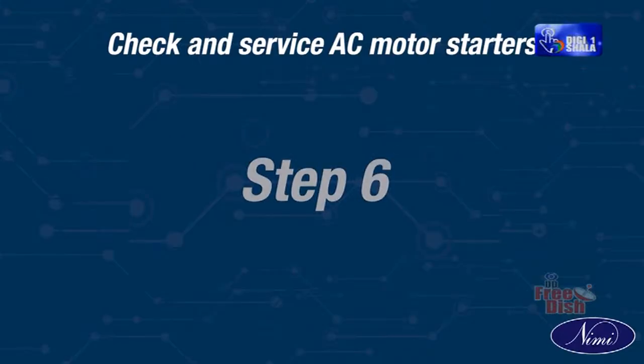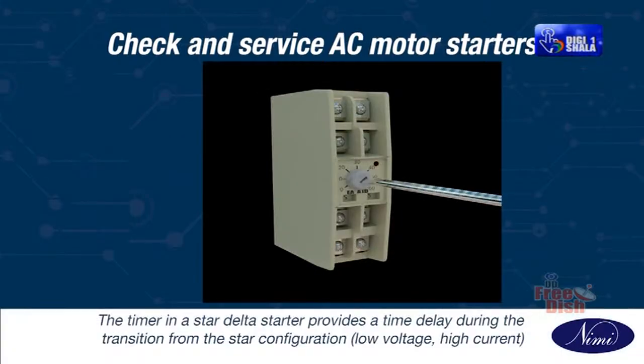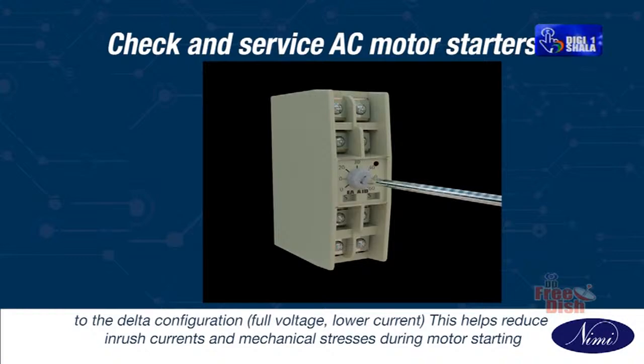Step 6. The timer in a star delta starter provides a time delay during the transition from the star configuration, low voltage, high current, to the delta configuration, full voltage, low current. This helps reduce inrush currents and mechanical stresses during motor starting.